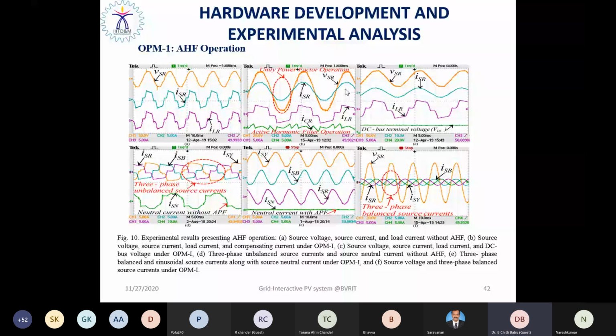And you see here, moreover, your three-phase AC current is in phase with the voltage, and the power factor becomes unity, right? In the meanwhile, see the source current is also sinusoidal and in phase with the voltage, but the load current is still a staircase because we connect a three-phase diode bridge rectifier load. Throughout the case, the DC link voltage or DC bus voltage is maintained constant, right? And the three-phase AC current is highly distorted as we connect the three-phase diode rectifier load, so that there is a strong circulation of the neutral current.